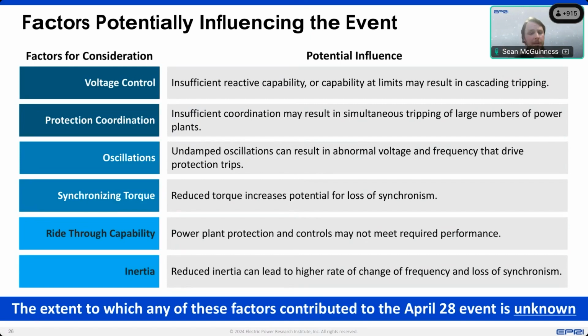And finally, inertia. Many grids which operate with high renewable resources set inertia floors. Setting an inertia floor is really about limiting the maximum rate of change of frequency and de-risking the loss of synchronism. But that's really a high-level capture to ensure that your grid remains stable. There are many factors underneath that, such as synchronizing torque, to ensure that your grid is actually stable and won't split apart.